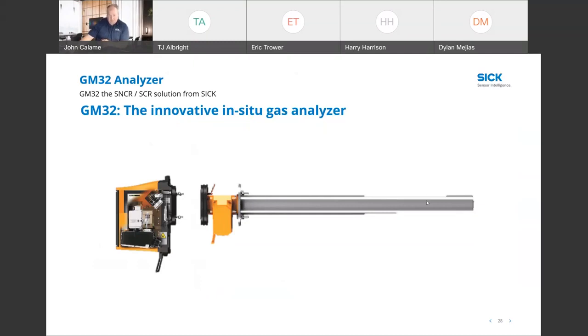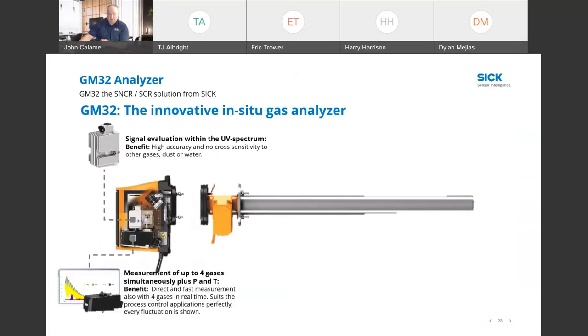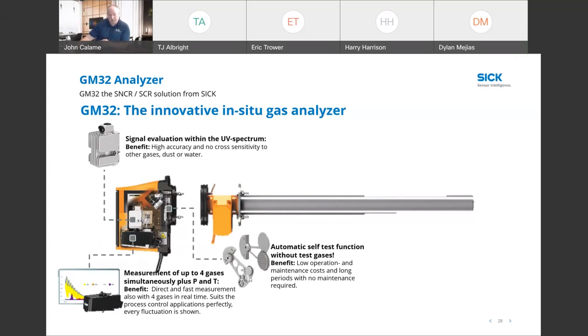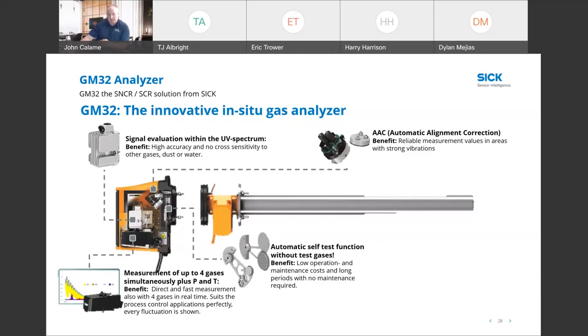It's hard to see here in this particular photo. This is your optical path, and it has a gas permeable probe on there, so it allows you to flood the optical path with gas for your quarterly validation verifications. So it uses a UV technology, so it's a UV lamp, and it can measure, as you said, the four gases plus pressure and temperature. And then, as we mentioned before, it can do the rotating fan filters and also the zero reflector to do your daily validations mechanically while the unit is functioning and online. And then there's an auto alignment correction as well to make sure all the optics are continuously aligned at peak performance. Dylan, did you want to add anything?